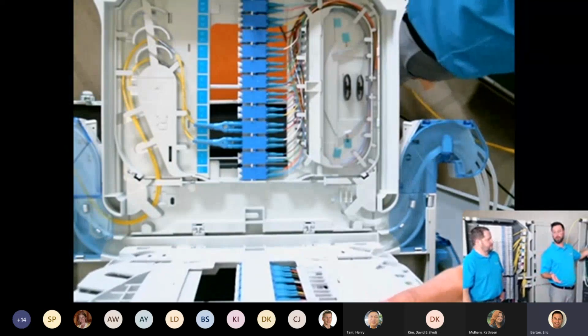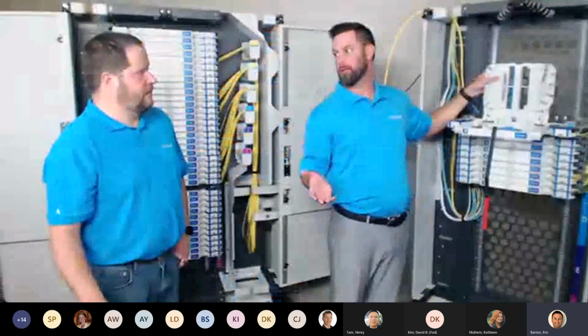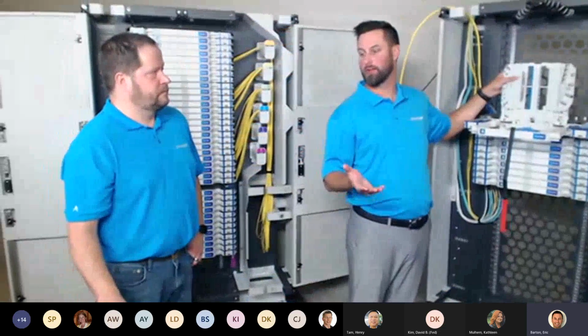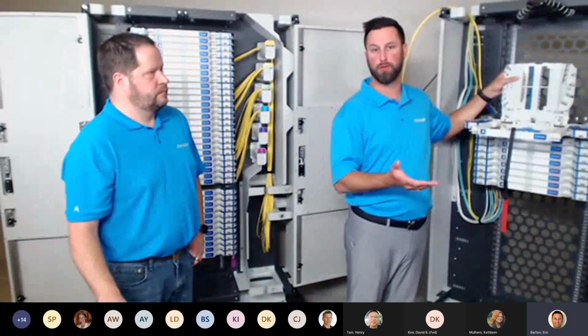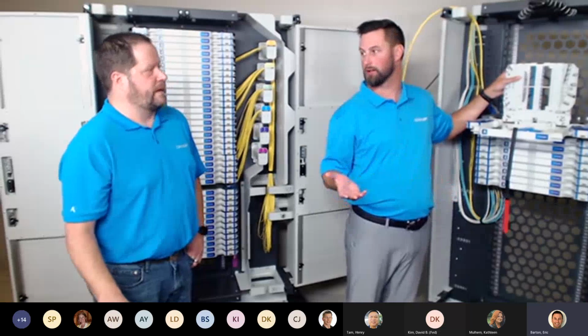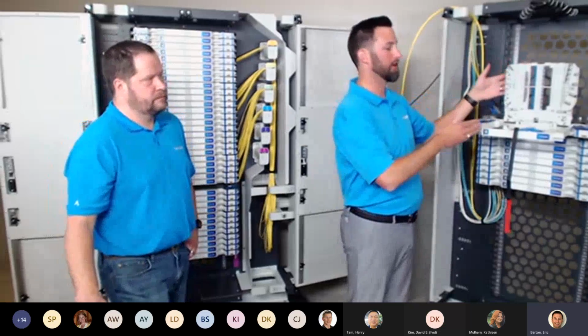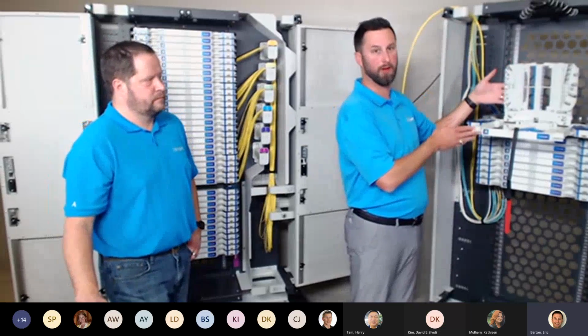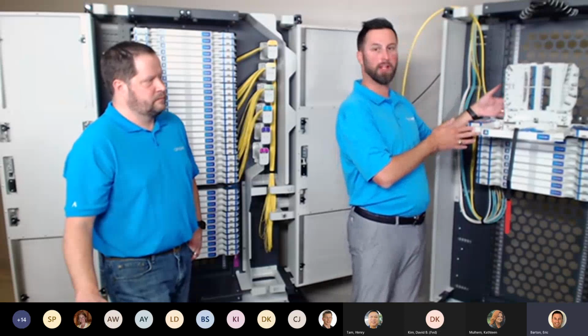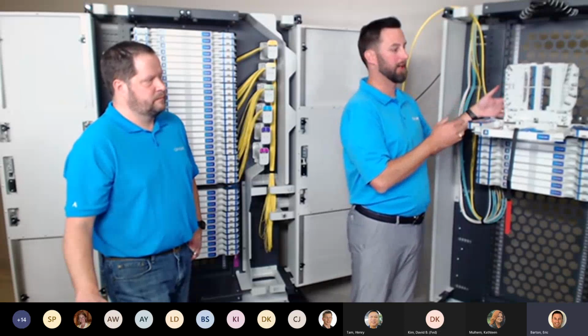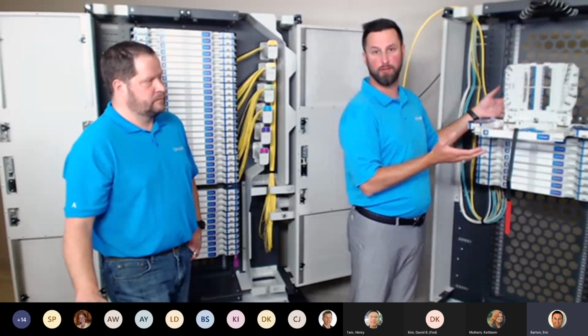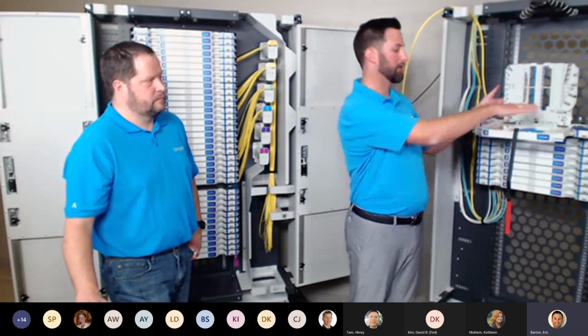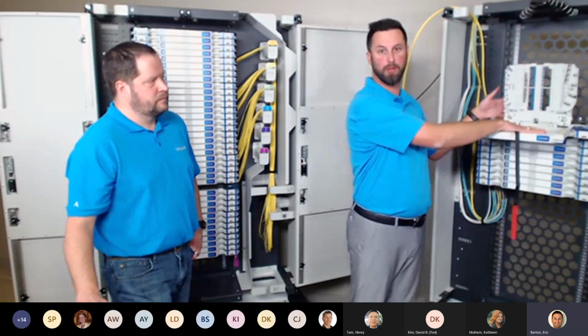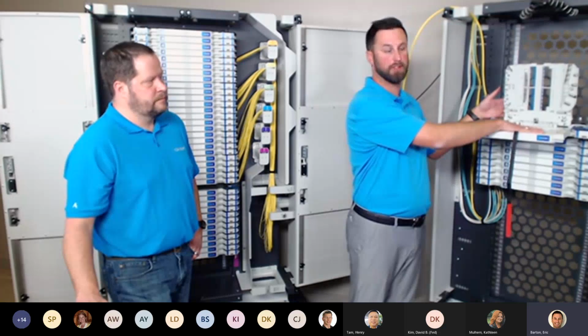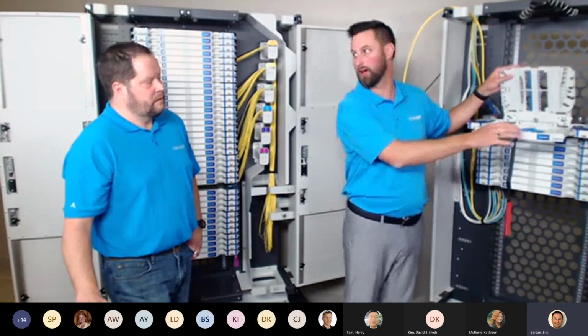For example, a 48 fiber, or let's go with the 96 count fiber, you'd normally order a 2 element for that. But you could also order it in a 4 element if you only want 24 fibers in each tray. So in this one, it'll accept 48 fibers, and you can run just 24. If you want to populate a 2 element piece that can hold up to 96, you could bring a 48 fiber into that and only populate the lower tray on each element, so you only have 24 fibers in each one.